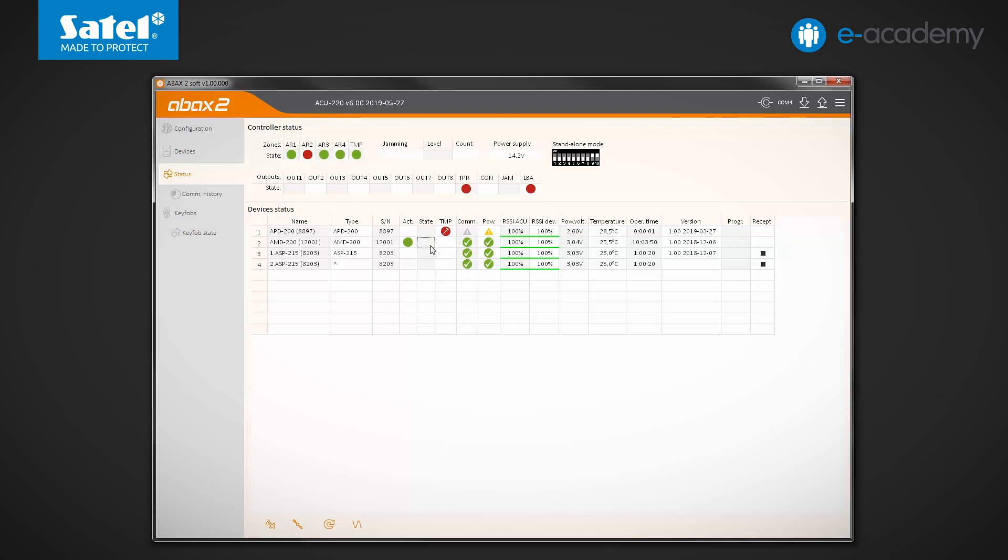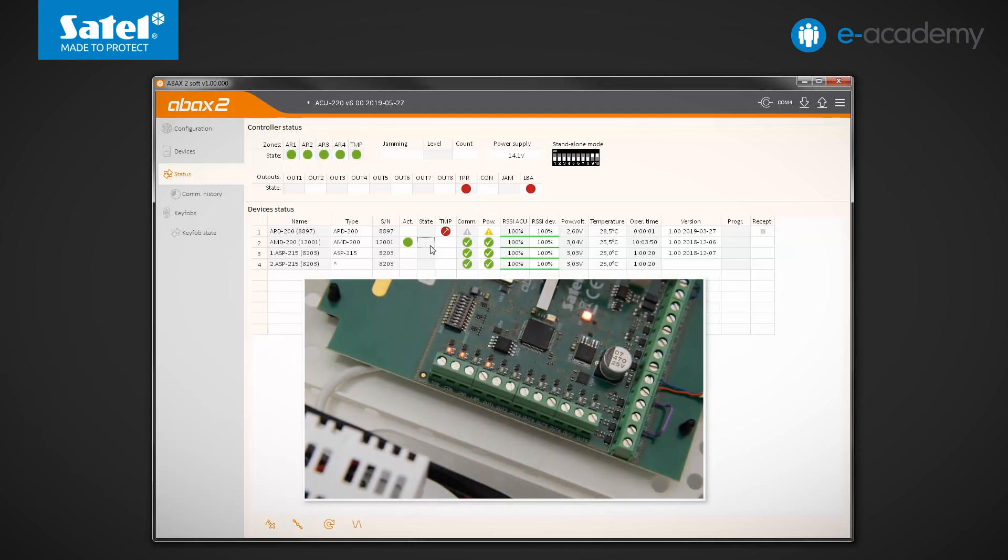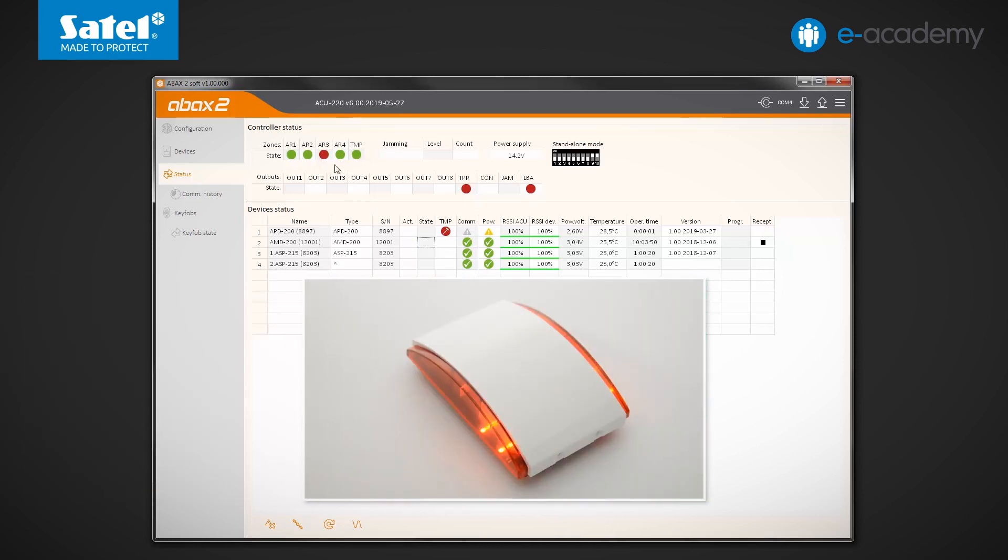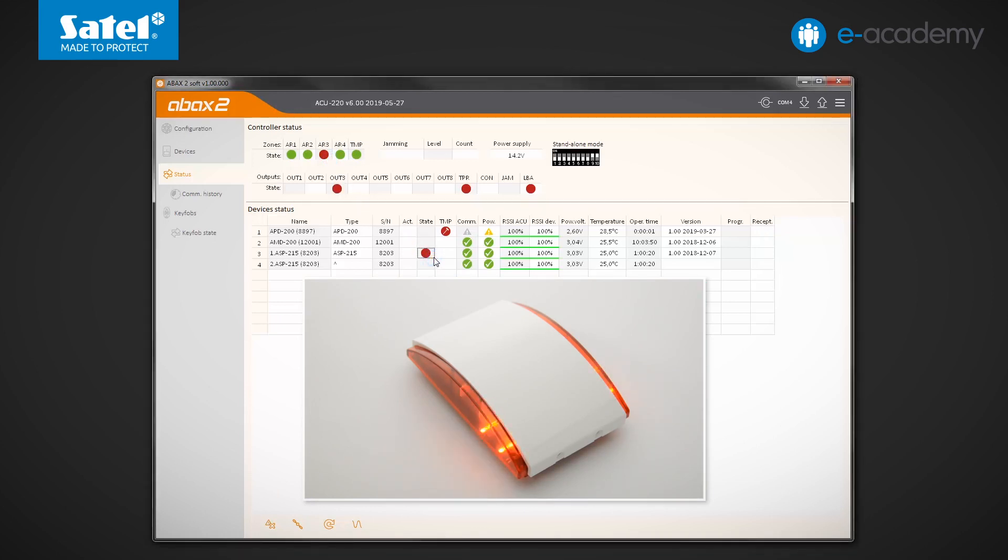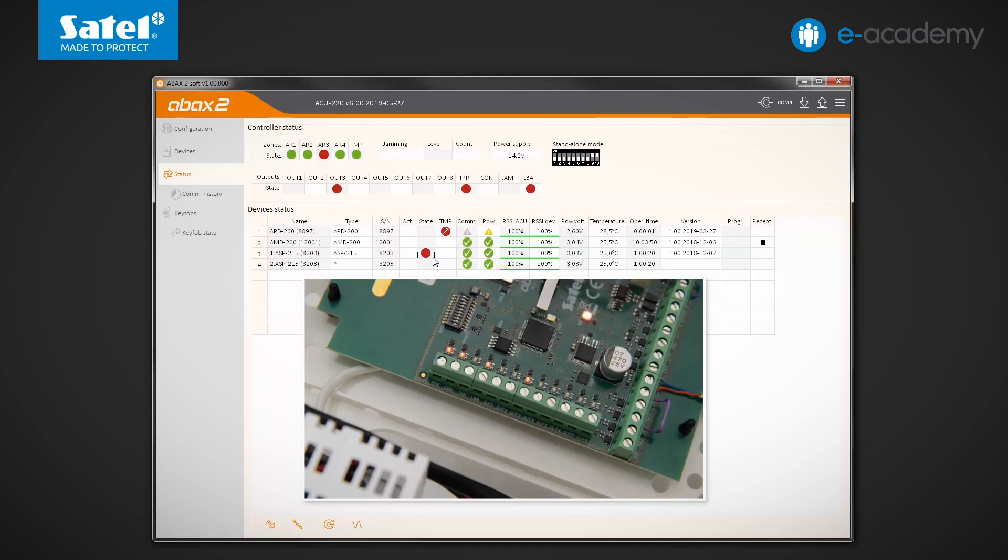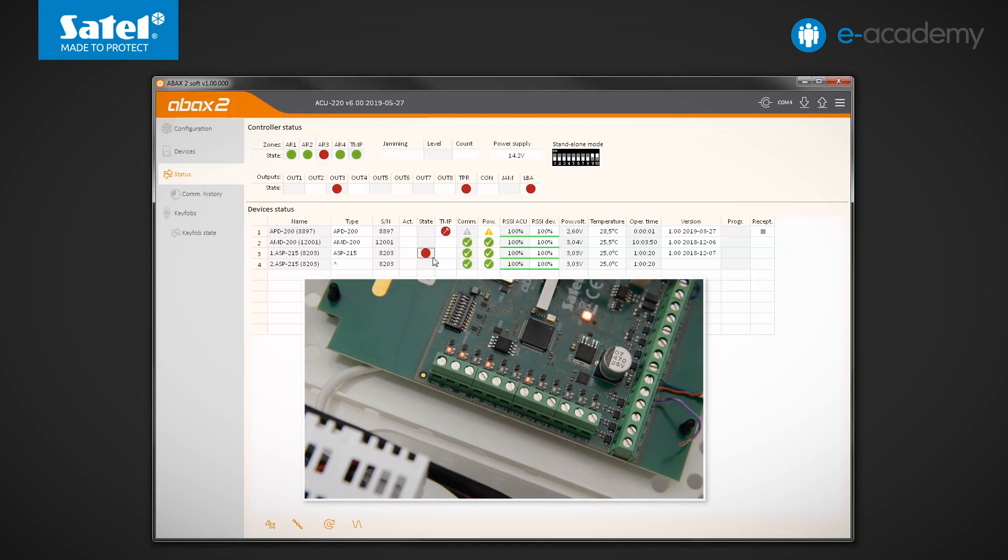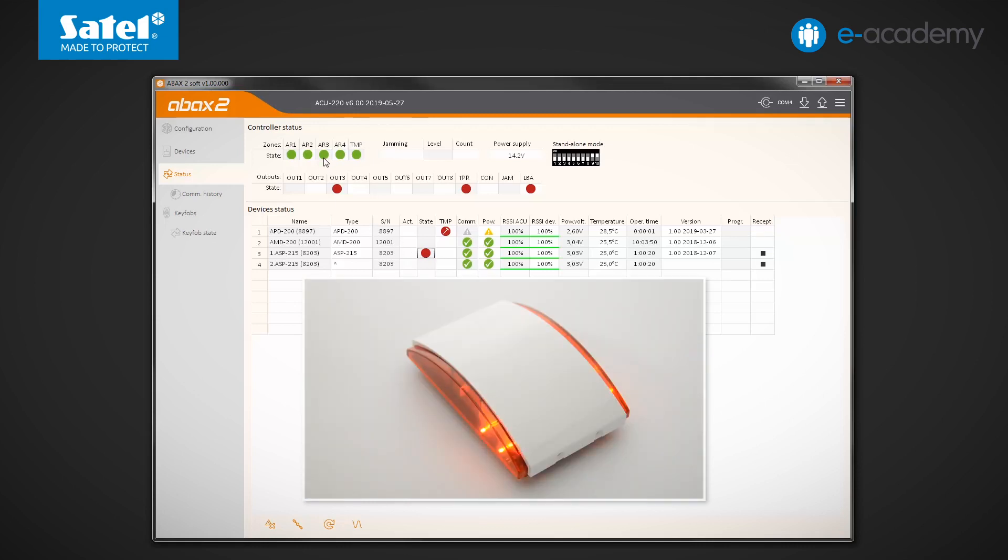The last device on the list is the ASP215 siren. In this case, the status field will show confirmation whether the signaling is currently active. To start the signaling, violate the AR3 zone. Optical signaling has turned on. There is also a red indicator in the state field. The siren will stop flashing after a specified time has elapsed or earlier if the control zone returns to its normal state and the siren itself receives the next periodic communication.